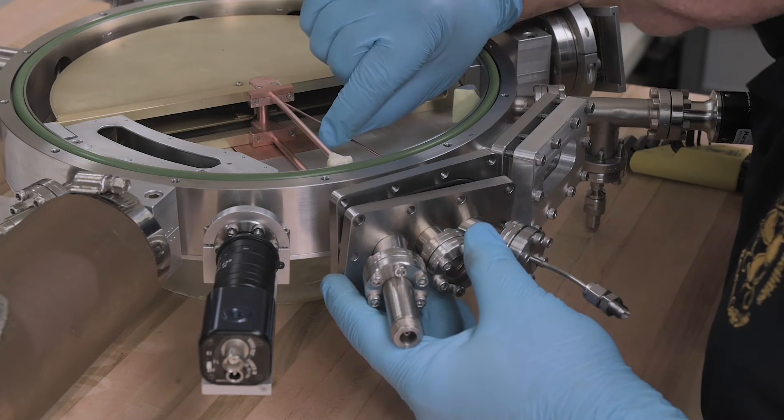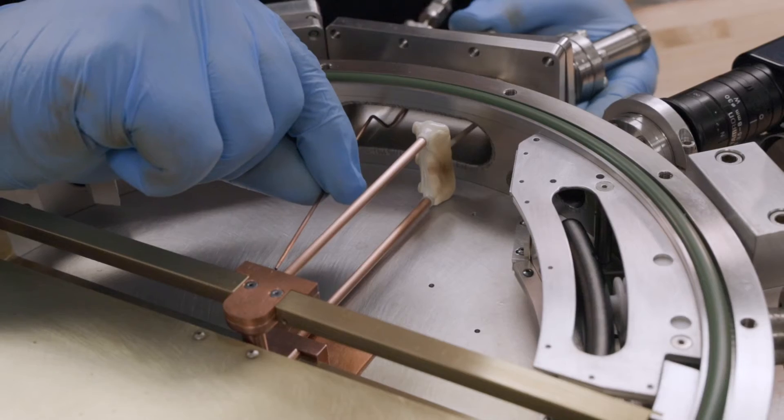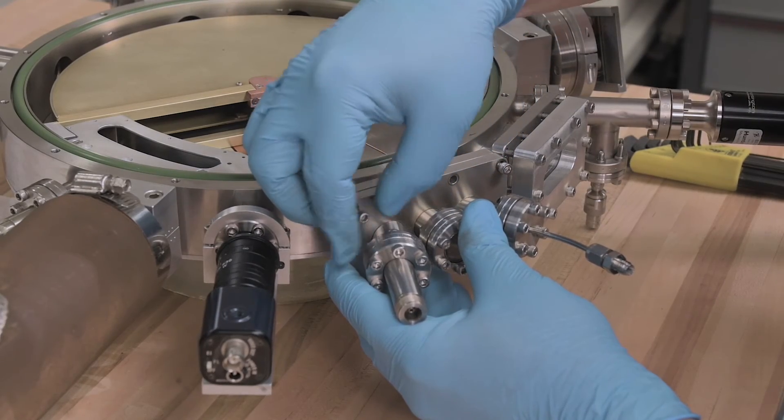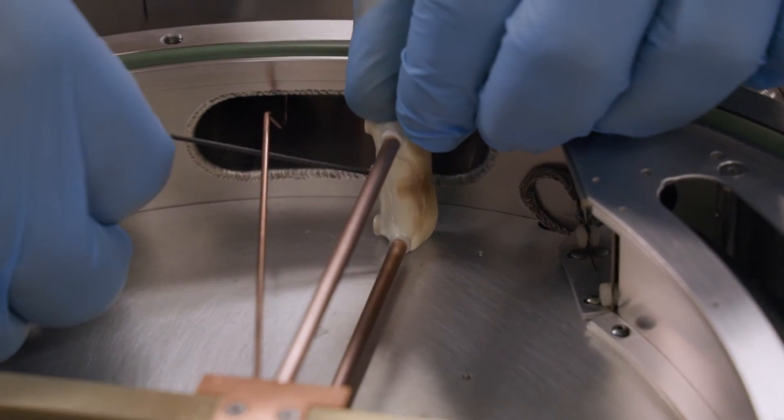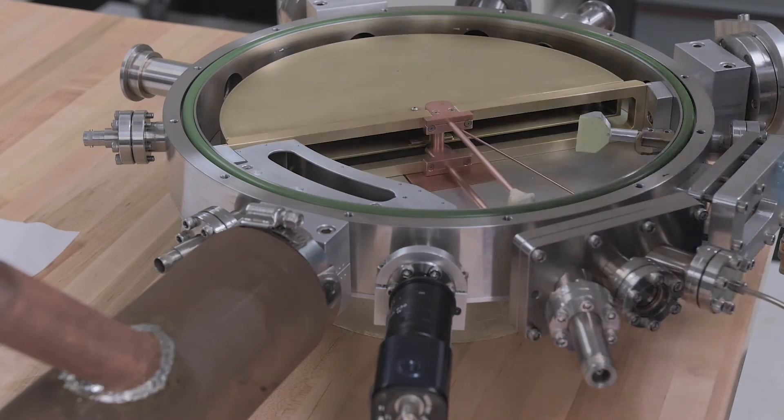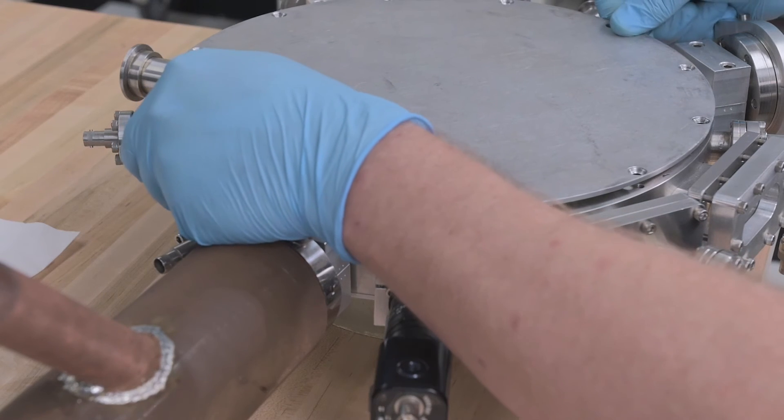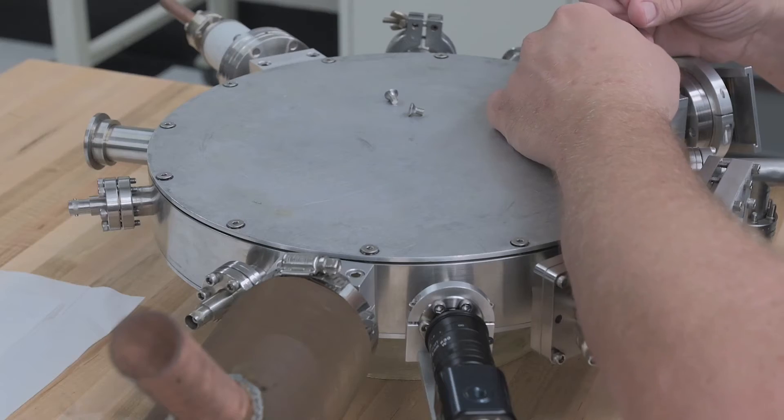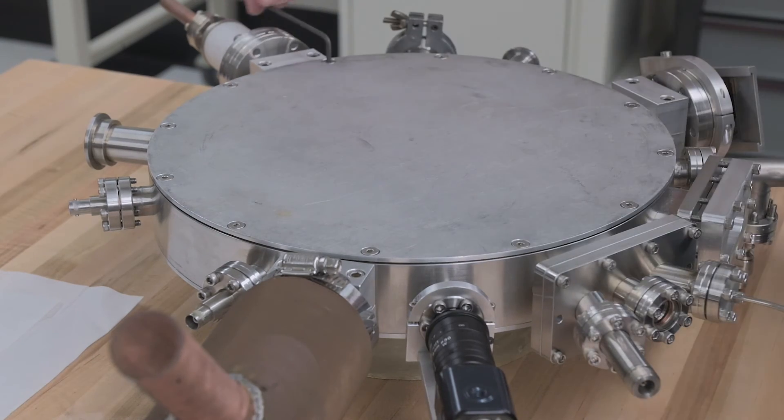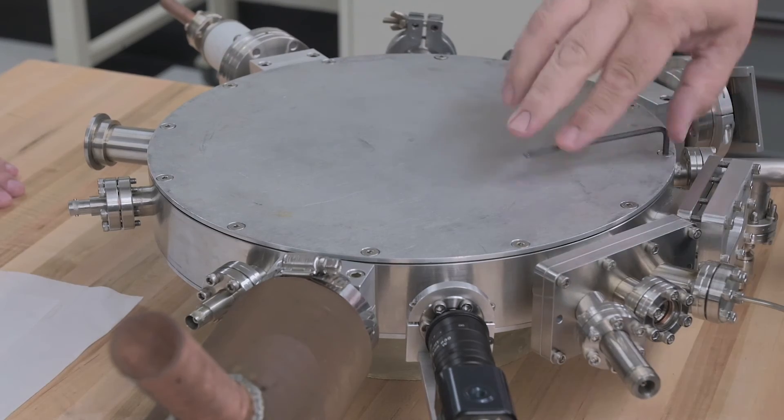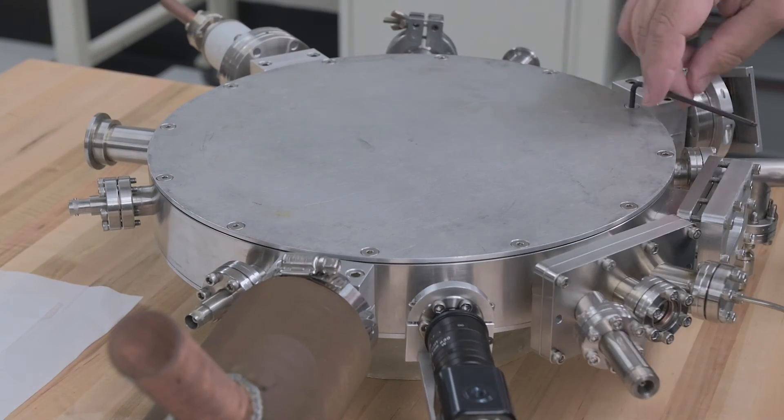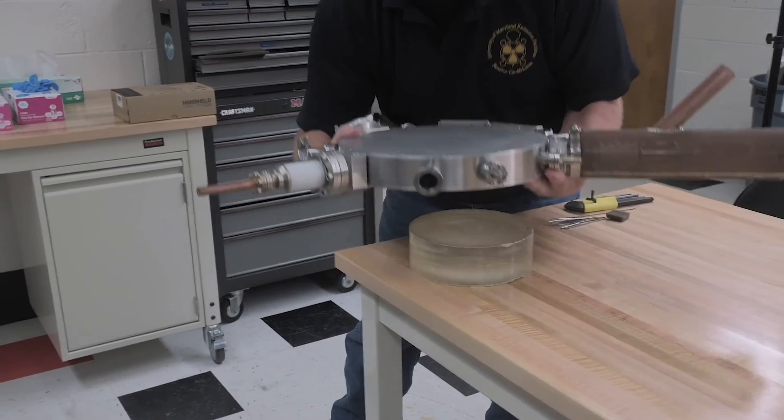I perform one final check to ensure the cathodes have not shifted and become shorted to ground. We seal up the chamber by properly using a star pattern tightening technique, then carry the chamber over and place it into the magnet's gap.